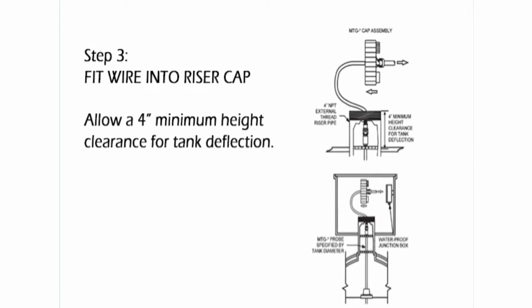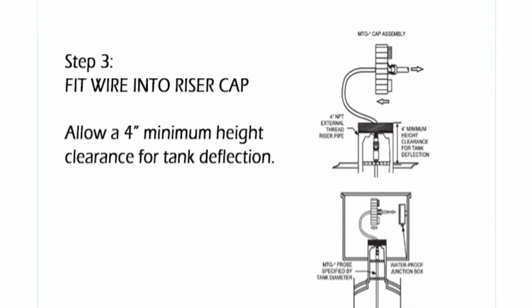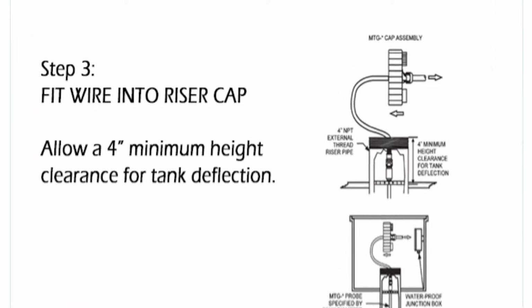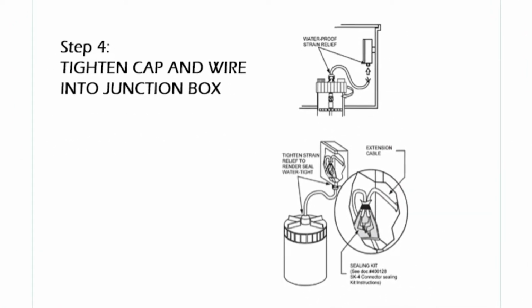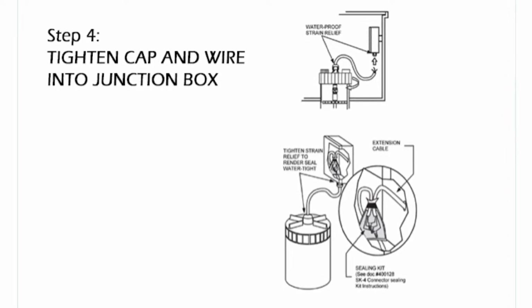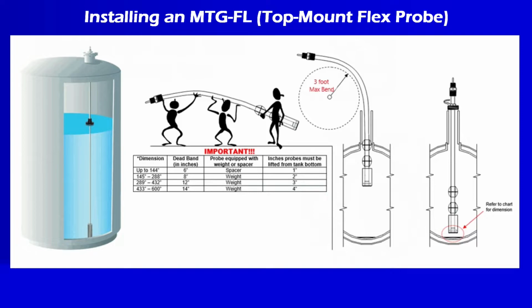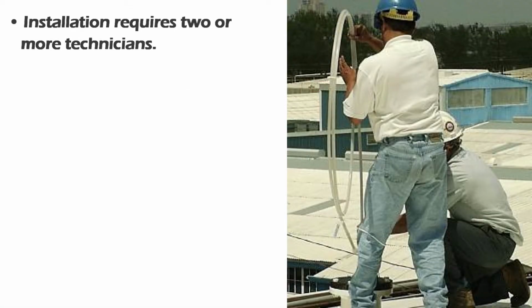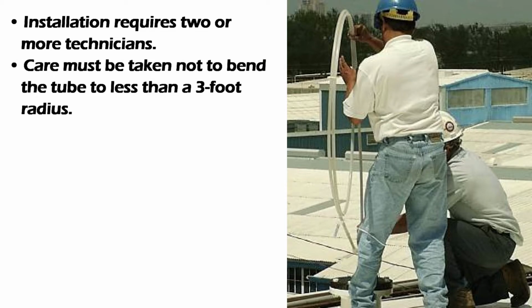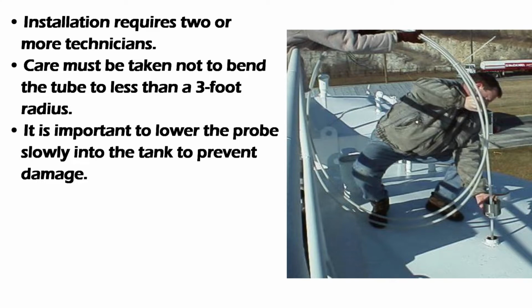Step 3. Fit the wire into the riser cap. Allow a 4-inch minimum height clearance for tank deflection. Step 4. Tighten the cap and wire into the junction box. The installation of an MTG-FL top mount flex probe should be done by 2 or more technicians. Care must be taken not to bend the tube to less than a 3-foot radius. Again, it's important to lower the probe slowly to prevent damage.